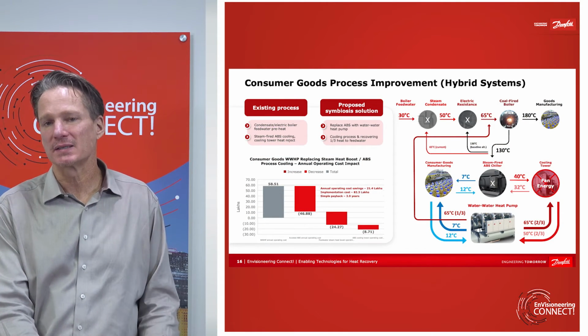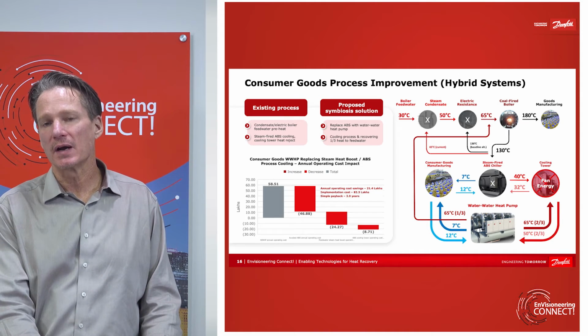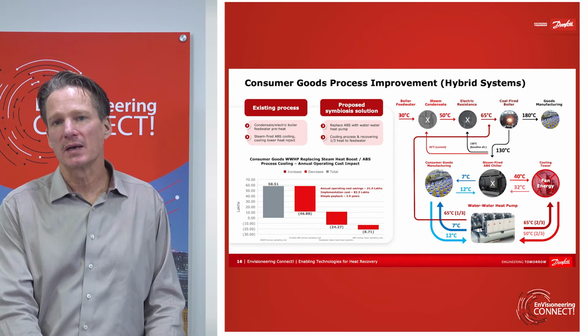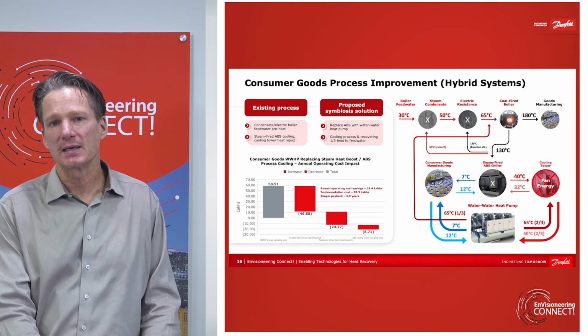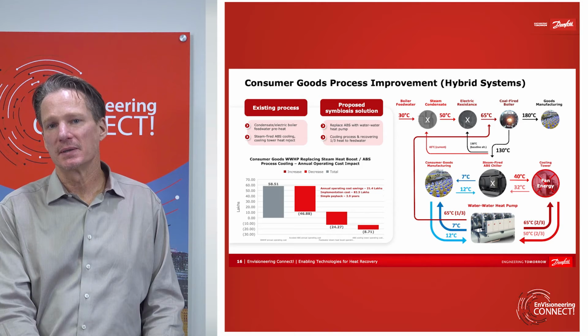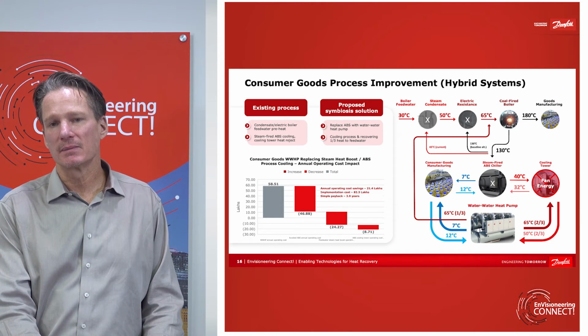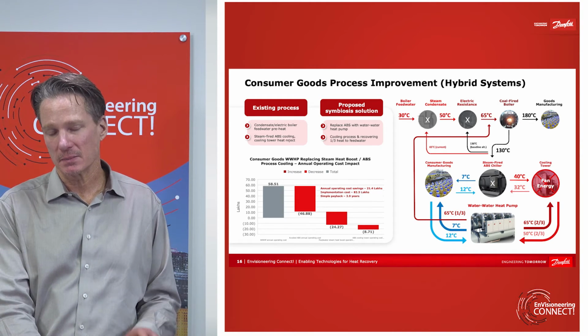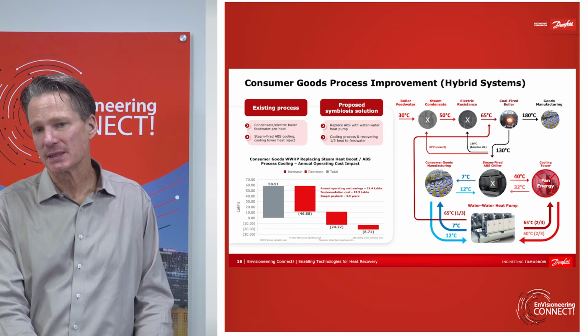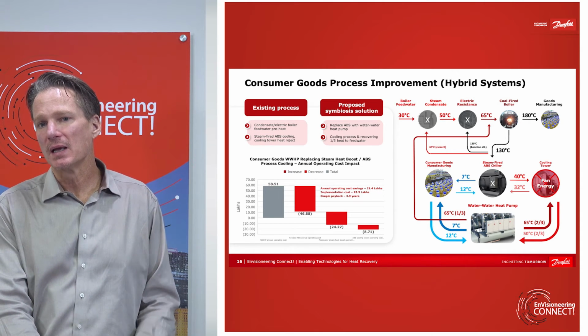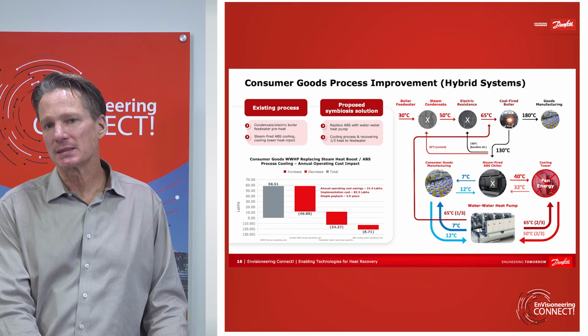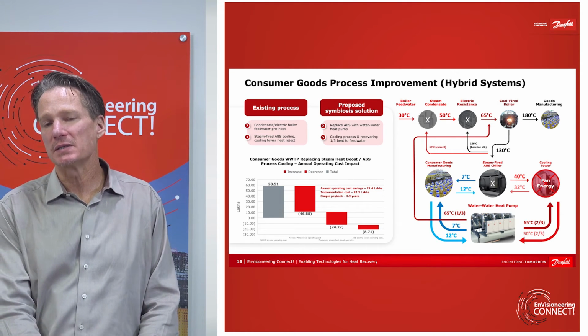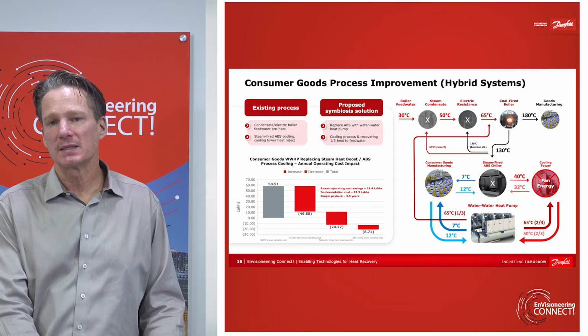Another example, and this is back to the industrial, this is again a very hard system to fully electrify because they're using both low pressure and high pressure steam, as you see with 130 and 180 degrees Celsius shown on the top right hand side. But what we do have the opportunity to do is take that system where they were taking that low pressure steam and running an absorption chiller based on it to provide cooling to an industrial process at the facility, replace it with a water-to-water heat pump that supplies the cooling to that industrial process, but then also recovers the heat to partially electrify their steam system.